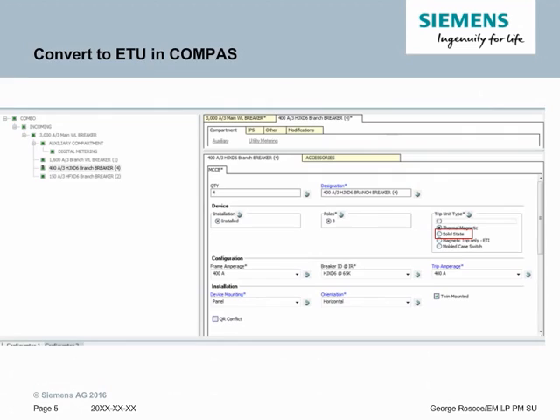Switching from a thermomagnetic breaker to an electronic trip breaker is as easy as changing the configuration on the main circuit breaker page. Under trip unit type, you see there is the selection for thermomagnetic. To change it to electronic trip, just select the solid state option and now you'll have a solid state circuit breaker.